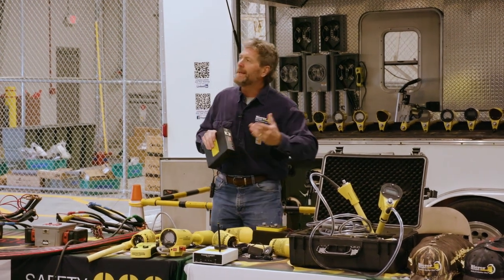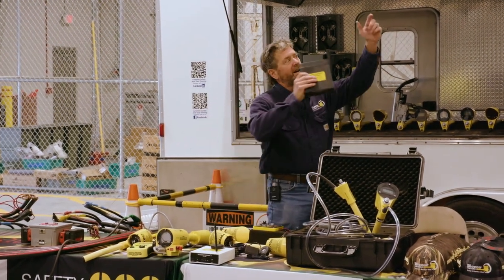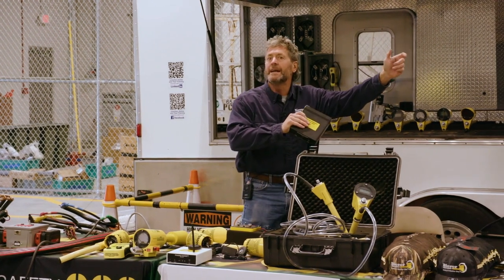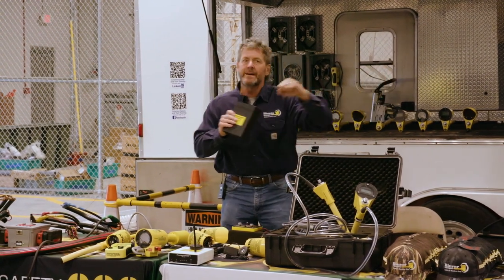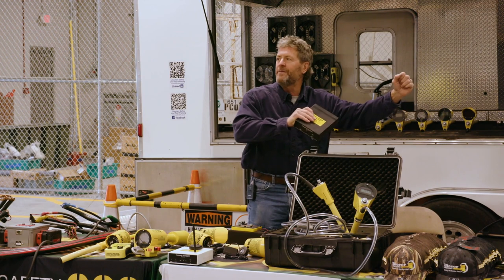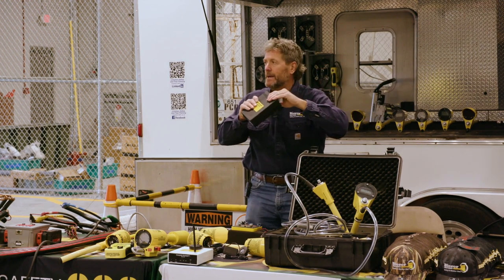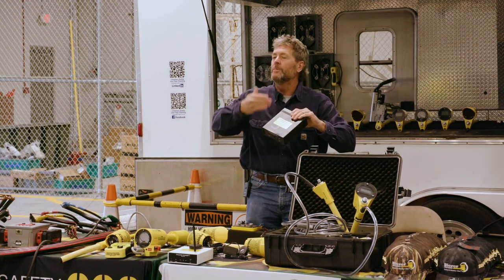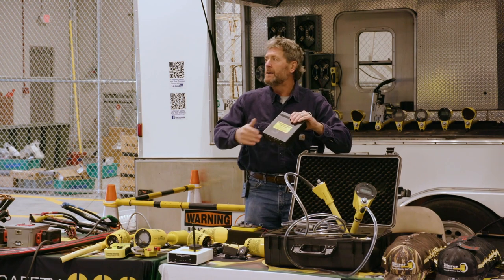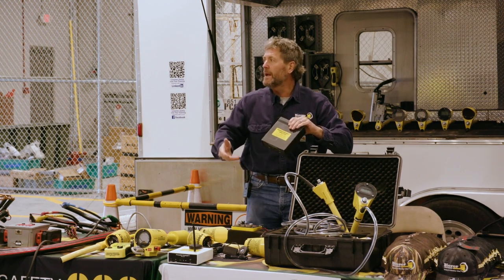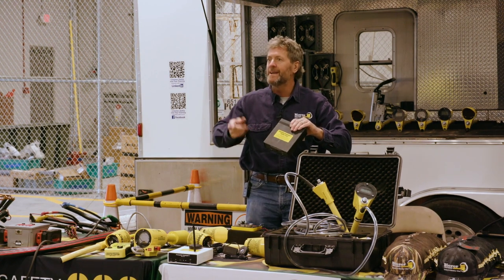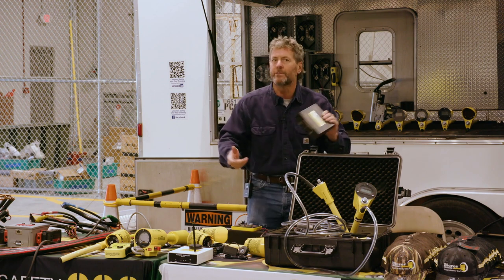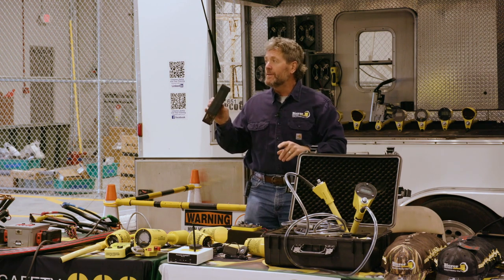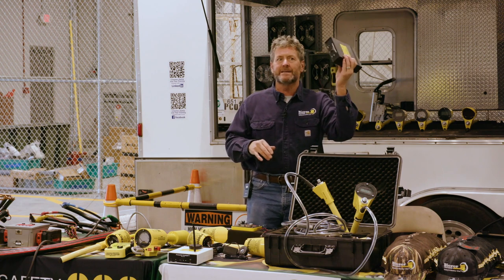When you take your PD800W and touch a known A phase, you're going to get zeros. Once you get zeros on a known A phase, this is calibrated. B will be 120, a blue light. C will be 240, a red light, once you calibrate it to an A phase. See how that works? It's real easy. Once you do that, you don't have to ever think about this device again.